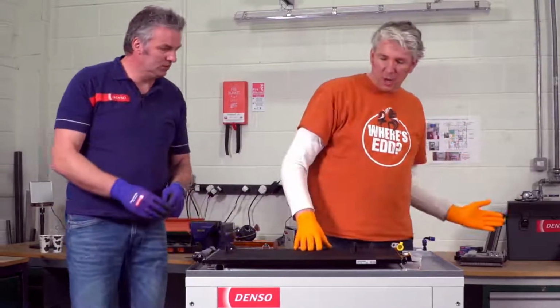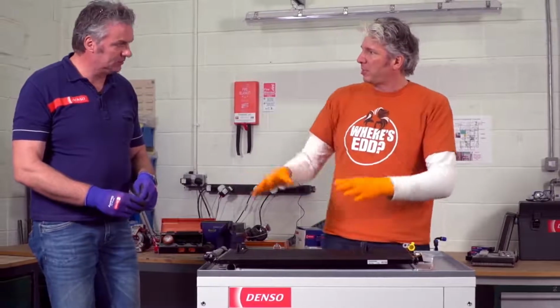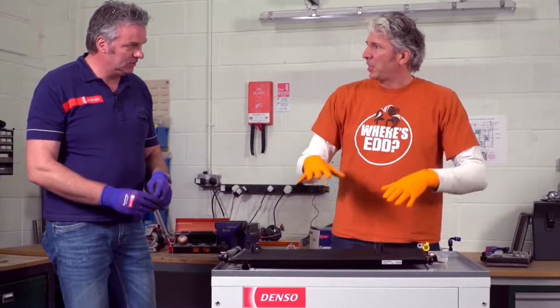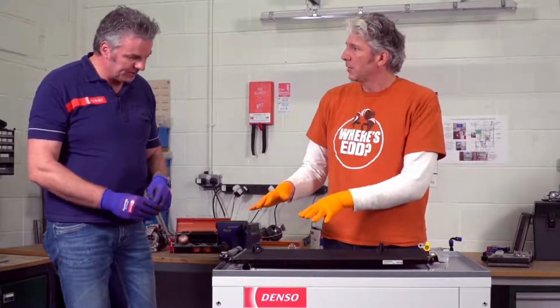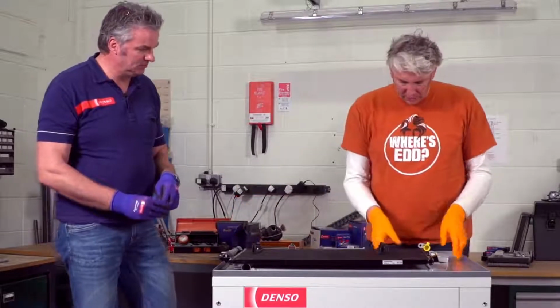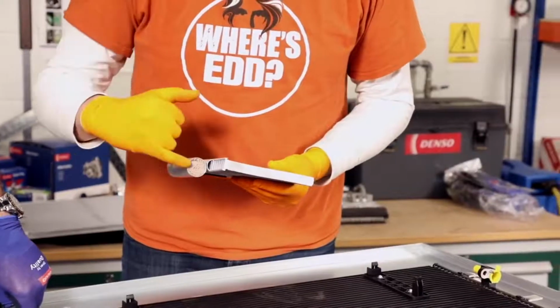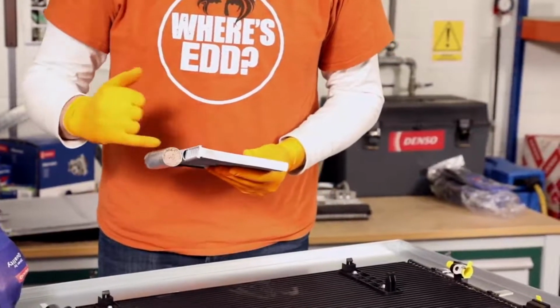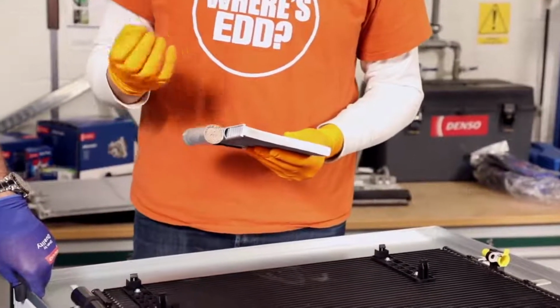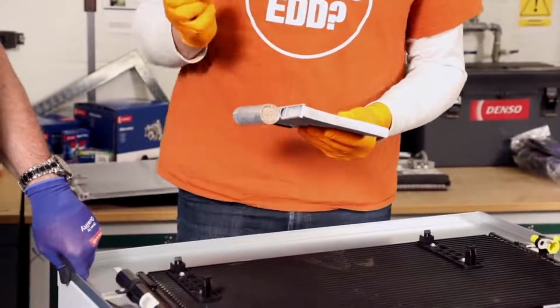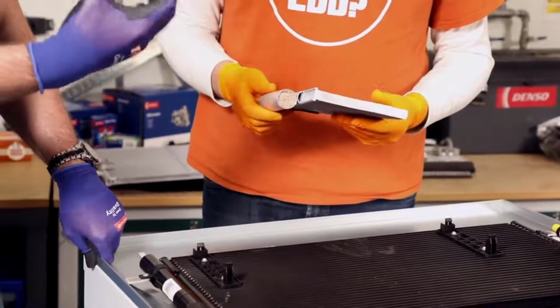Right, so as our hot gas comes in from the compressor, it gets turned into cold liquid. Exactly. And that's the condensation. Yes, that makes perfect sense. And actually, it's quite nice. We've got a little cutaway here, so you can see inside all these little balls of zeolite, and that's what's removing the moisture. They're hygroscopic. So they like water, and they catch the moisture inside.